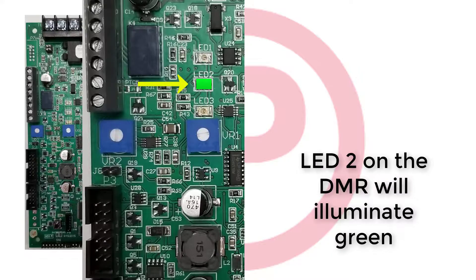The Potter voice panels have five LEDs on the DMR which will help guide you through typical troubleshooting processes. Upon normal conditions, all LEDs will remain off besides LED 2, which is green and means the system is in a normal status.